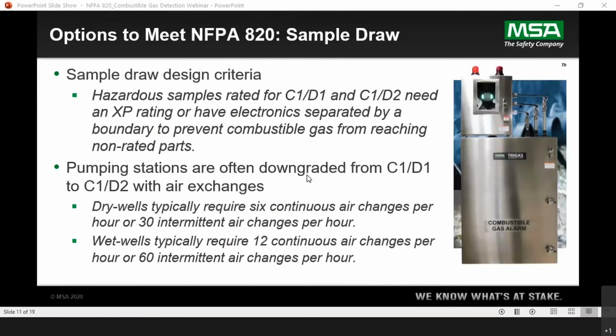So for example, if you have an open circuit in a box and you're pumping hazardous material that contains methane gas, you want to make sure it's separated, because methane gas could potentially light off inside an enclosure with open wiring. It's interesting to note, for pumping stations, that is a very common application. Some of the samples are without ventilation, a Class 1, Division 1 situation, but a lot of users will downgrade the Class 1 Division 1 to Class 1 Division 2 by doing air exchanges. For dry wells, you need 6 changes per hour or 30 intermittent air changes per hour, and for wet wells, 12. So that just gives you an example of what's done out there.